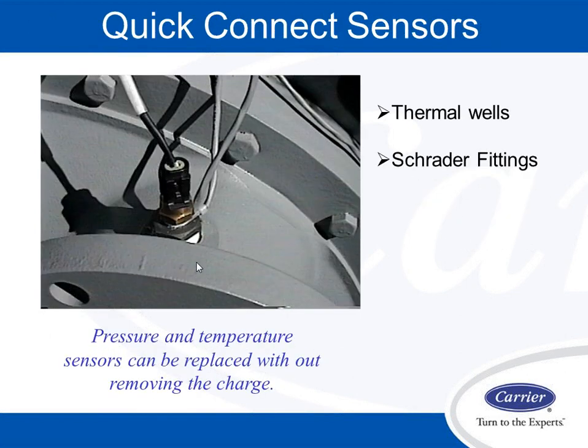Quick connect sensors, again, I said the little things. If you change out a sensor, I don't have to remove the complete charge of refrigerant out of the machine to do it. With the thermal wells and the Schrader fittings, we can simply change the sensor out. Very nice situation.